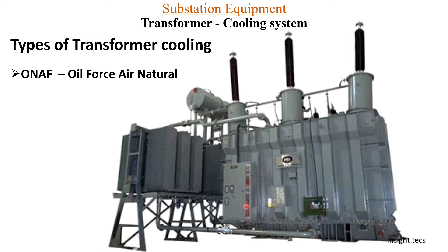An oil force air natural transformer will look like this — the radiators are given separately from the main tank. Through the pipes you can see the oil is being circulated using a pump. This is a higher rated transformer and in this kind of transformer you can see oil force air natural cooling system.